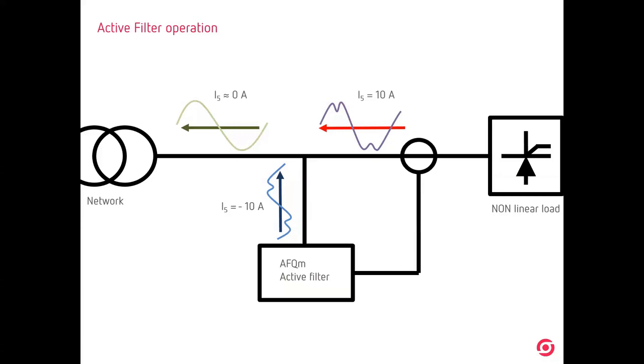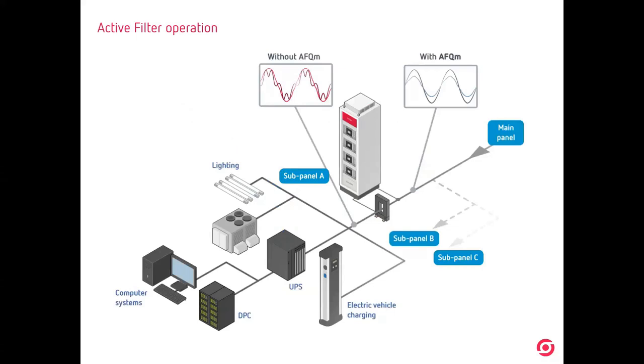We are not saying that we are always reaching zero value. It will depend on the current of the filter, but we will reach a value very close to zero. Okay? What we want is to get a very low value of current that will not create any kind of risk for the installation. If the filter is oversized, obviously we will reach zero amps. And this is how it works. You are inside an industry. You have LED lighting, computers, UPS, data processing centers, electric vehicle recharge, that will create harmonics.